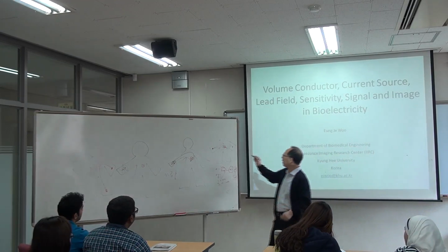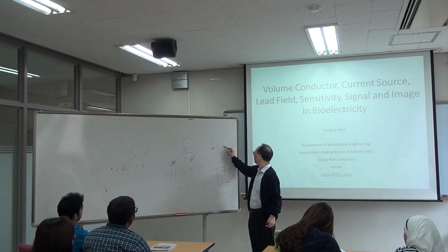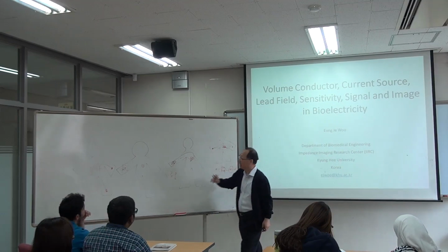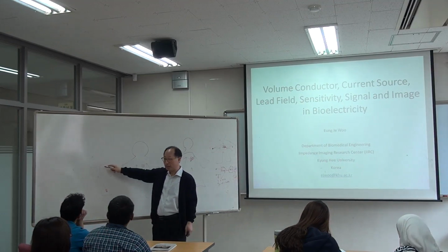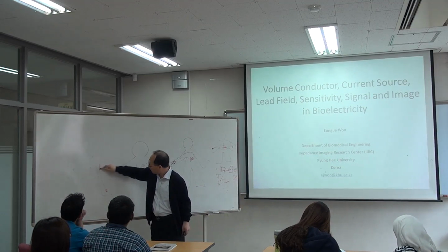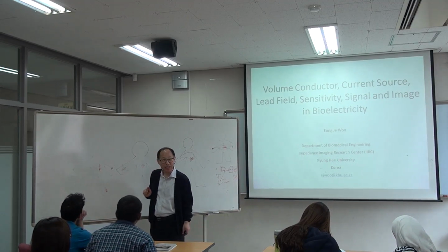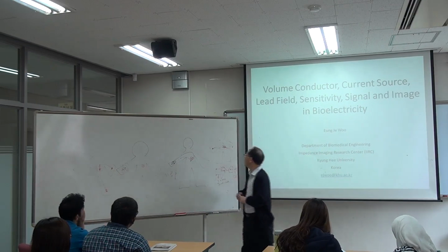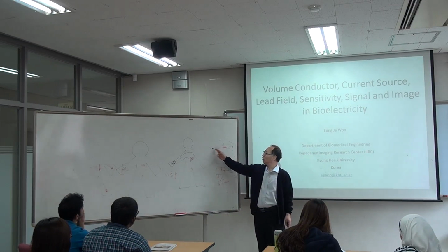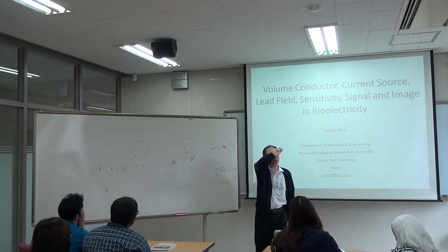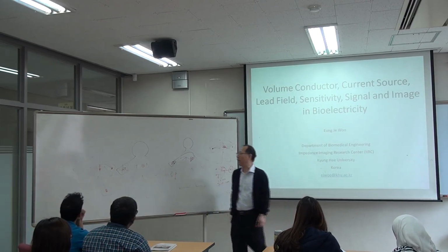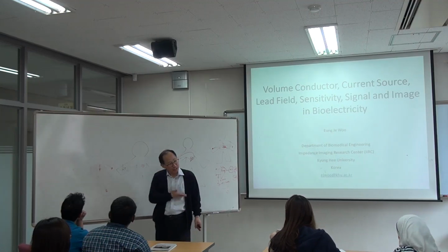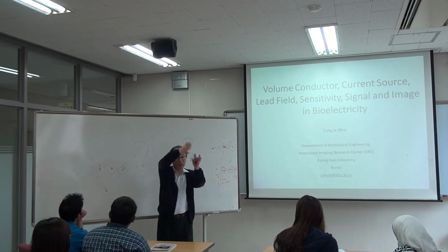And so we have a horizontal lead vector for this kind of electrode configuration. And in this case, we have a vertical lead vector. Now we are measuring ECG using these 2 electrodes as the first channel, and we are measuring this ECG as a second channel. So we are displaying ECG in 2 channels.